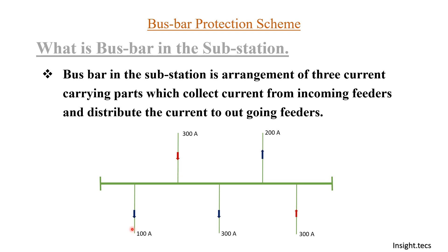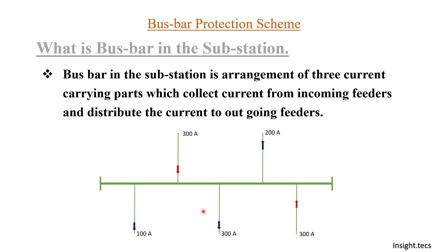So the bus bar protection scheme basically continuously senses the difference of incoming and outgoing current. If the difference is zero, the bus bar is safe and no protection operation is required. If there is some difference between incoming and outgoing current, that means there is some fault that has occurred on the bus bar, and in that case the bus bar relay protection scheme will come into picture.